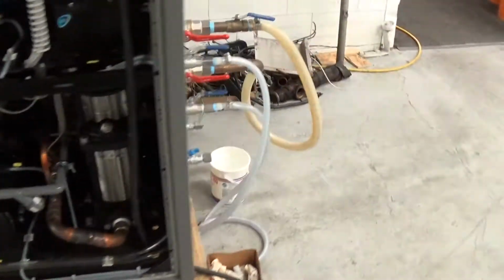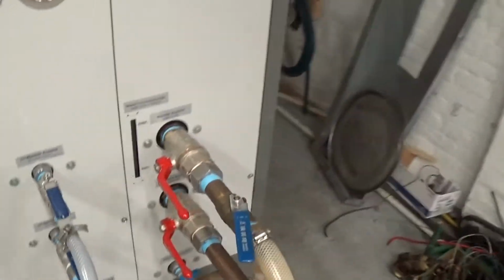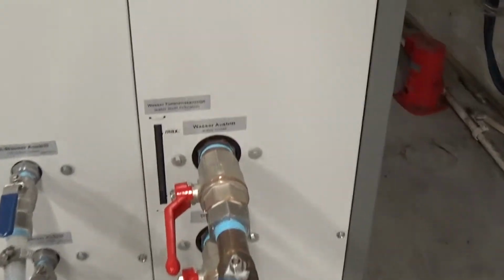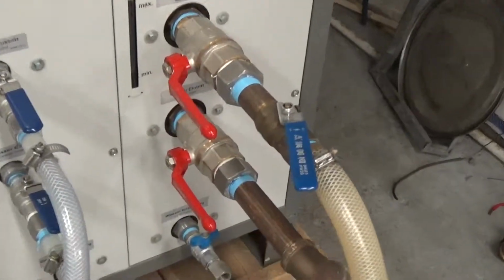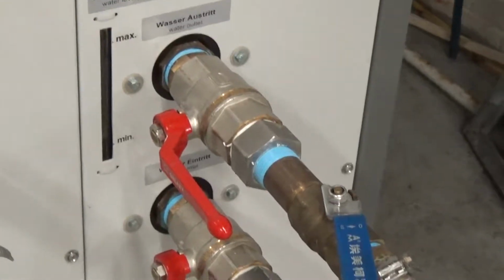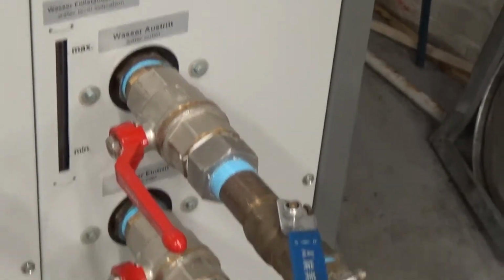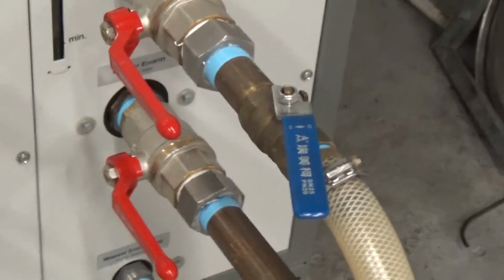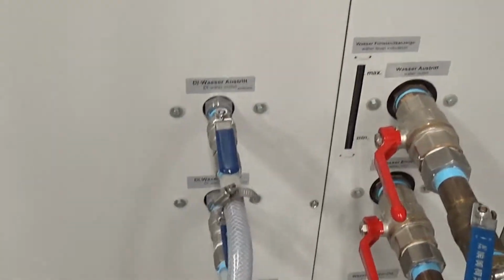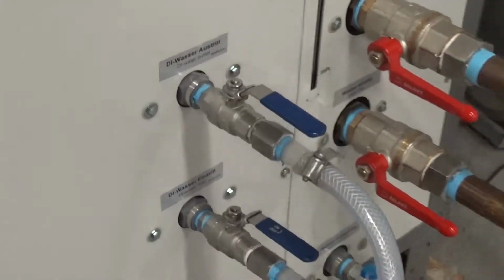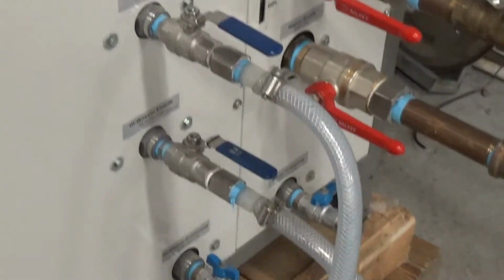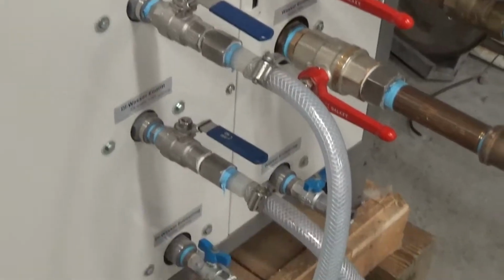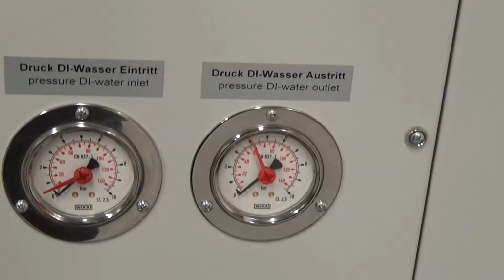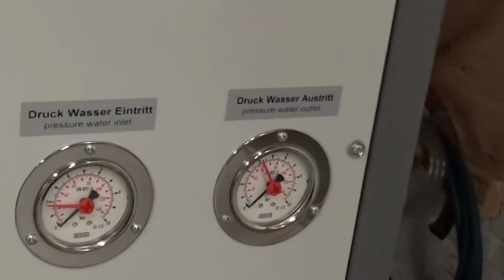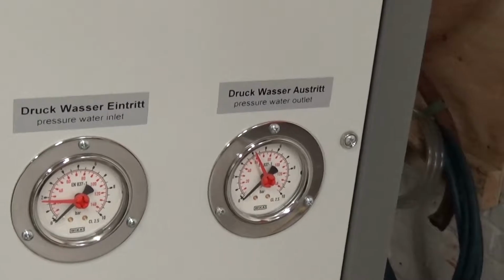What that means is all your cooling is going to come through your bigger connections here, the water outlet. Okay, and these nice fittings, the red handles, those are going to come with the unit in a box. So your water outlet and water inlet is going to go to your primary process. These two smaller ones here, which in the world of laser cutting they refer to as the DI or optic circuit, that's simply just going to be plugged. Similarly, the DI water inlet and outlet pressures aren't going to be operating, but the primary ones for the pressure water inlet and outlet will.